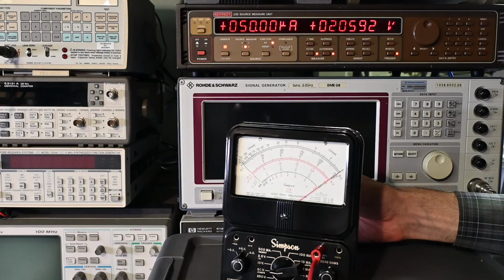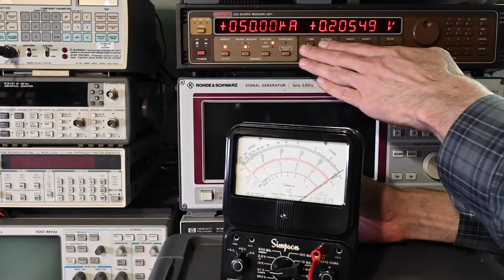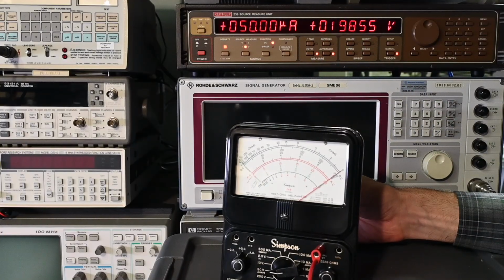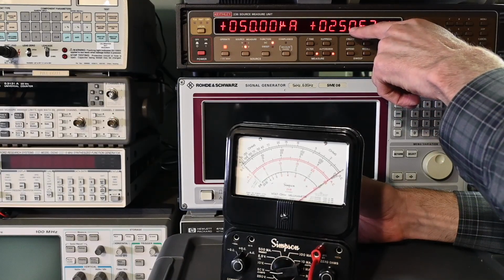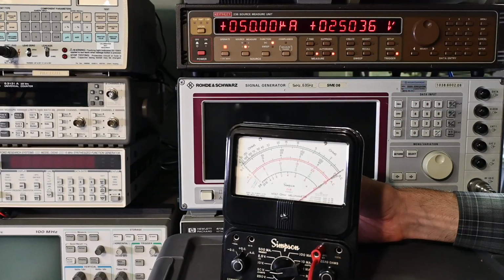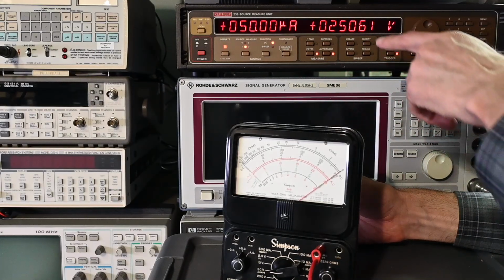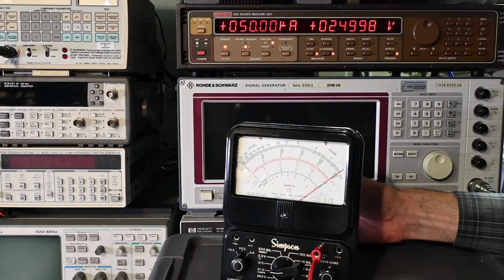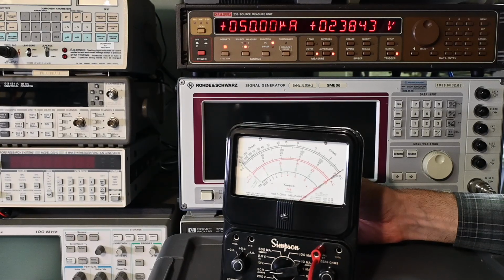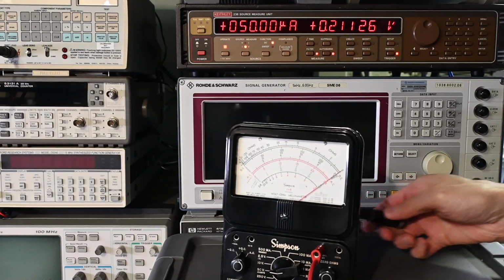So that's not how you want to calibrate this. This needs to be in the constant voltage mode. And if I turn this a little bit further here, let's go all the way over, right about there. So notice this is now at 250 millivolts. That's actually right about where it needs to be for the calibration, because now it's 250 millivolts and 50 microamps. But it really needs to be done with a steady voltage, so we need to put this into the constant voltage mode. So I'm going to just turn this back down again, put it right about there.